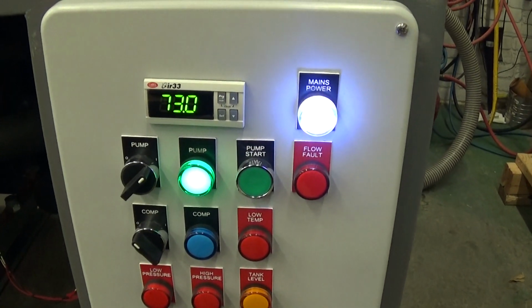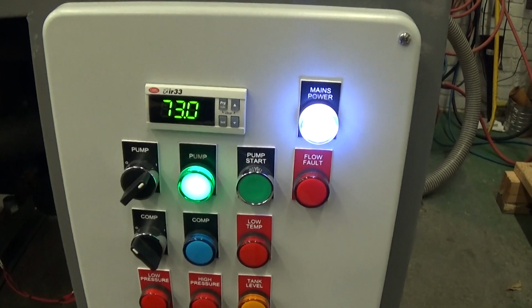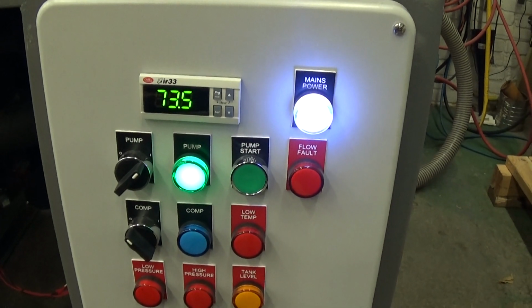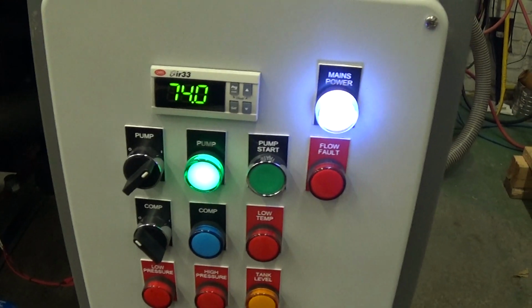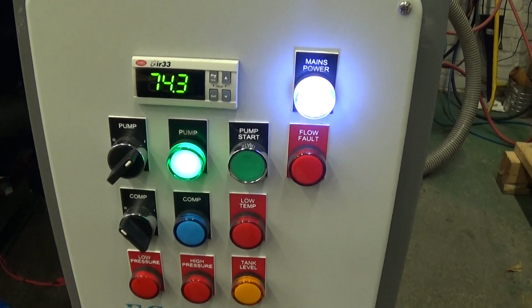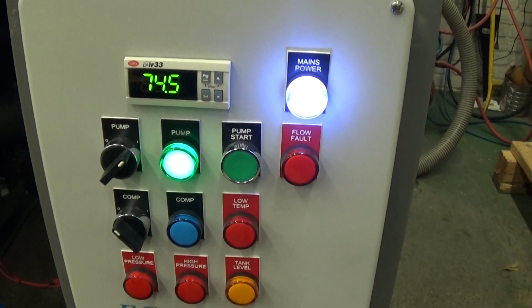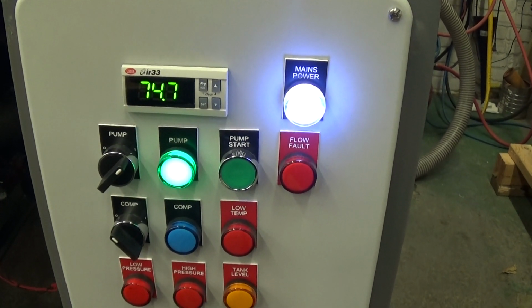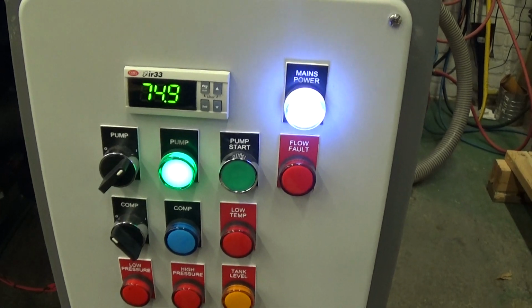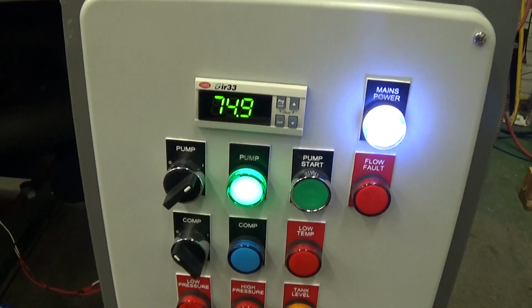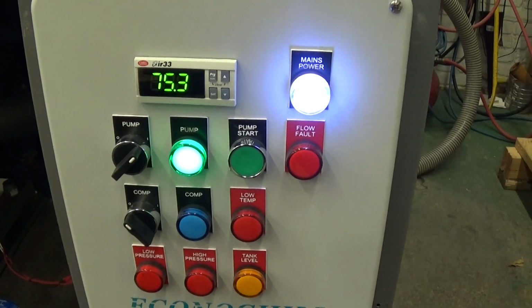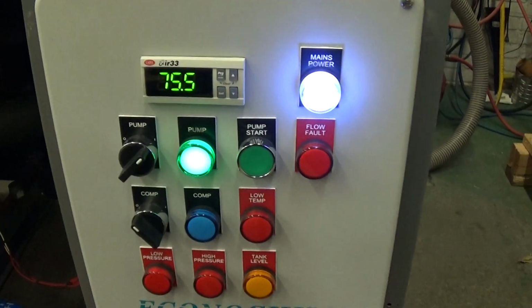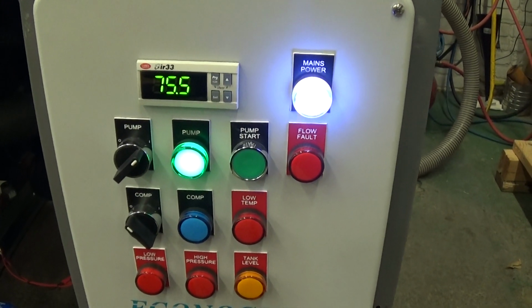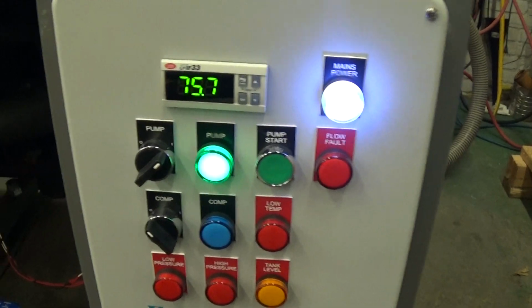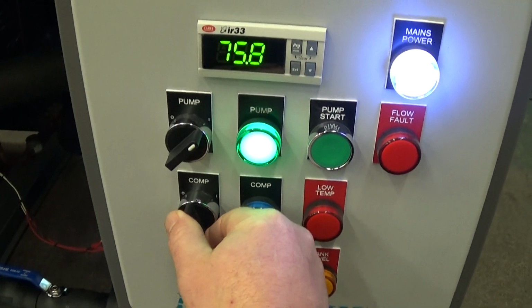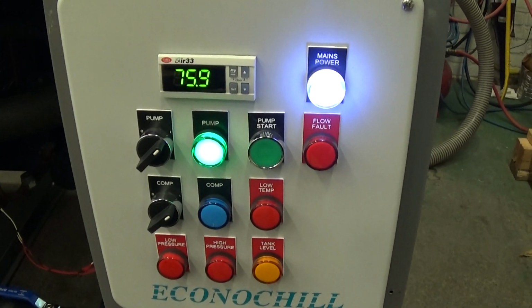Now when you turn the pump switch on, the pump comes on, and the pump should always stay running. The pump start here is only needed in the event of a power glitch to reinitiate the pump. Otherwise, on initial startup, just turn that pump switch, and the pump indicator light will come on. Then what we're going to do is we can turn on our compressor. That gives us the cooling.